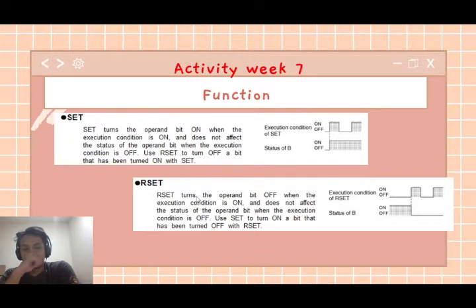This is the function of set and reset. Set turns the operand bit on when the execution condition is on, and does not affect the status of the operand bit when the execution condition is off. Use reset to turn off a bit that has been turned on with set. This is a bit memory for set. You can see when it turns on, the status bit will remain on.